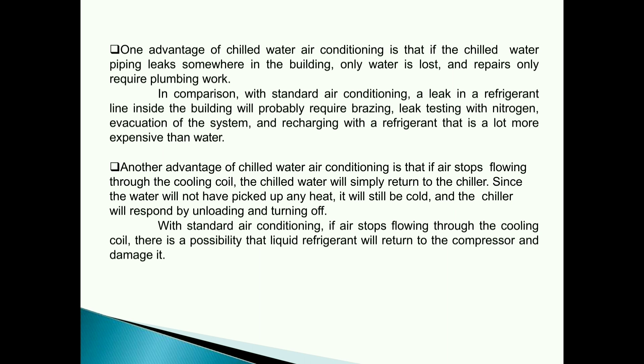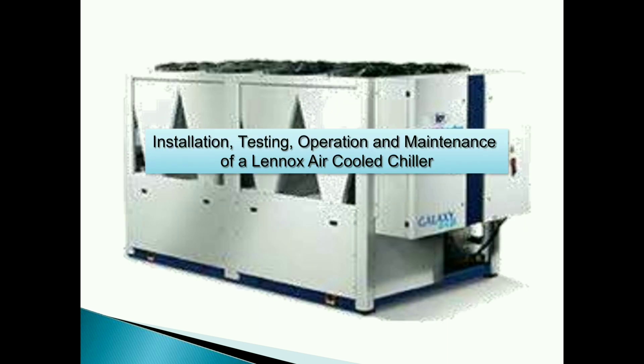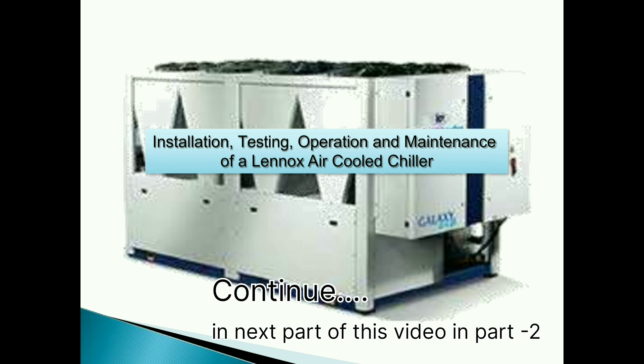Another advantage of chilled water air conditioning is that if air stops flowing through the cooling coil, the chilled water will simply return to the chiller. Since the water will not have picked up any heat, it will still be cold, and the chiller will respond by unloading and turning off. With standard air conditioning, if air stops flowing through the cooling coil, there is a possibility that liquid refrigerant will return to the compressor and damage it.